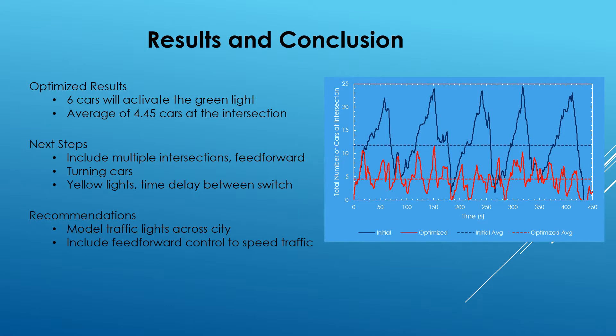The way we optimized the controller was by manipulating the trigger value. We used a sensor for the number of cars on the north and south sides of the intersection as the basis for our controller. We determined that with an activation point of six cars on the north and south sides, that gives the minimum average number of cars at the intersection. The high points on our graph show the unoptimized parameters — about 20 cars before activation. Changing it to six cars dropped the average to 4.45 cars at the intersection at any given time.